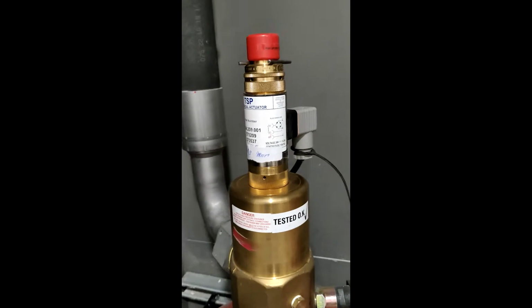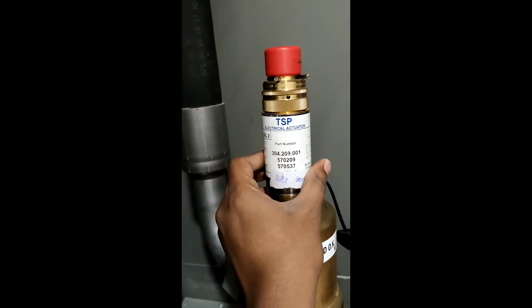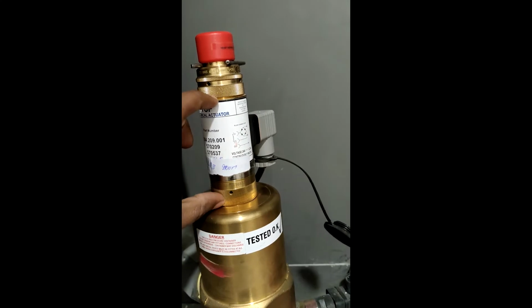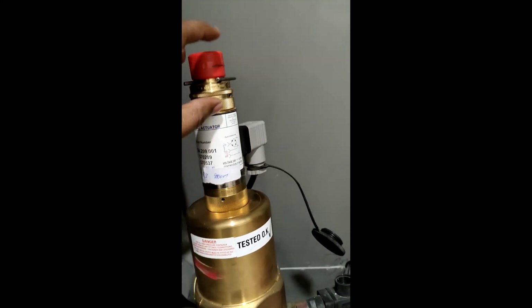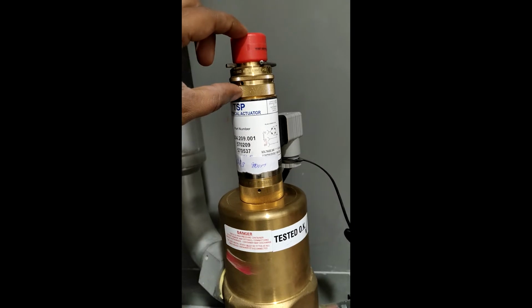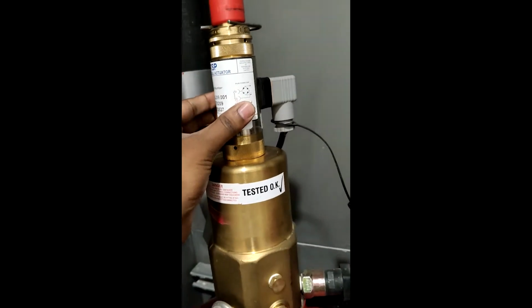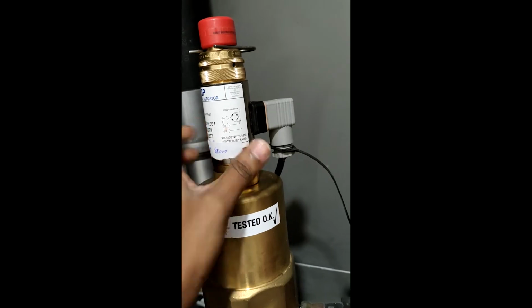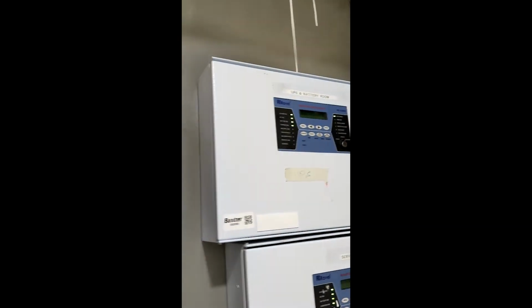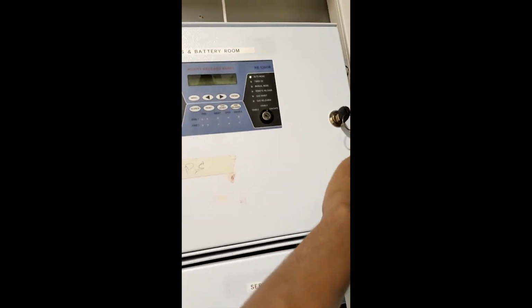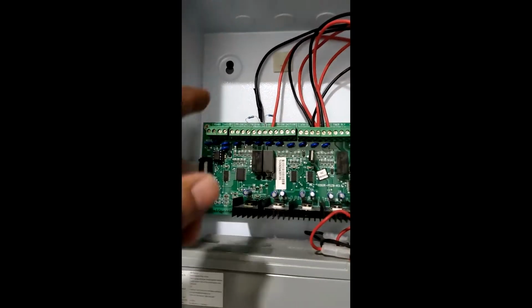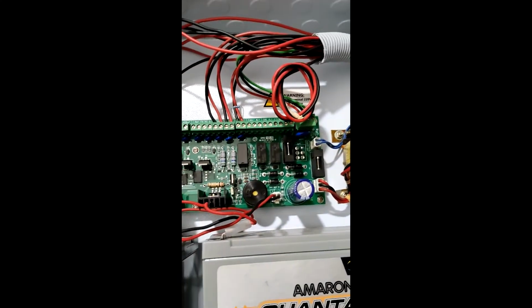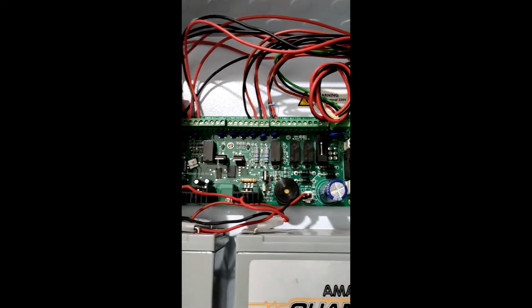Okay, and if we come here, we can see the actuator. Here it's the electrical actuator, and this is the mechanical actuator, or manual actuator. See, the electrical actuator is connected. You can see this cable which is connected to it. From here it's going and connecting to this panel. Inside this panel, see here it's connected. Some zones are connected here, and detectors are connected here.